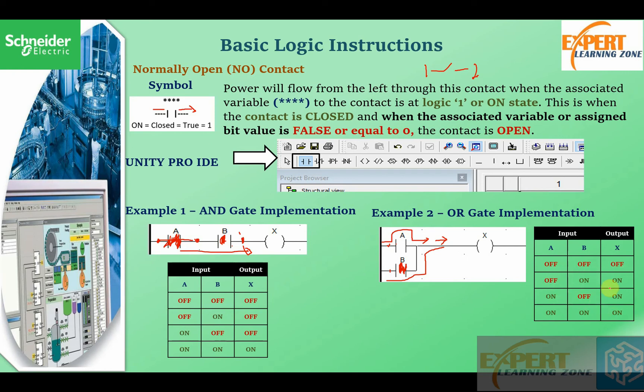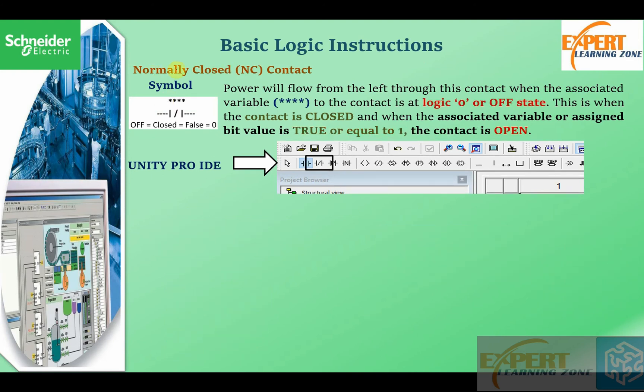Now the normally closed contact: power will flow from the left through this contact when the associated variable is at logic zero or off state — this is when the contact is closed. When the associated variable or assigned bit value is true or equal to one, the contact is open. So it is just the inverse of a normally open contact.